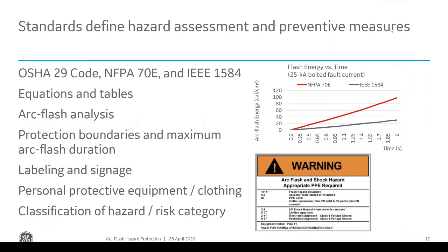The term arc flash has very much crept into electrical jargon in the last few years, because previously we weren't taught much about arc flash. We designed our equipment as best we could. But because of the safety issues associated with arc flash, it has become a very critical part of our assessment and prevention measures. A lot of the time, we spend a lot of time and money in design to mitigate arc flash incident energy so that we can reduce the risk and hazard for personnel.